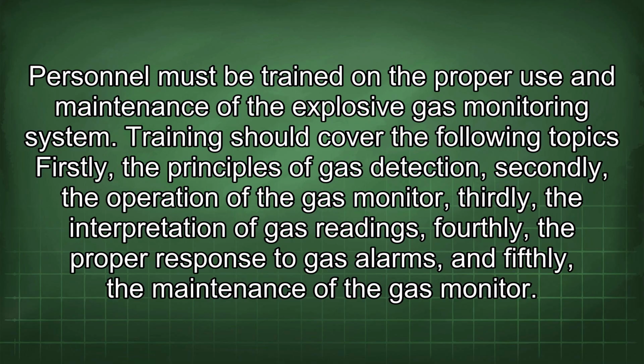Personnel must be trained on the proper use and maintenance of the explosive gas monitoring system. Training should cover the following topics: firstly, the principles of gas detection; secondly, the operation of the gas monitor; thirdly, the interpretation of gas readings; fourthly, the proper response to gas alarms; and fifthly, the maintenance of the gas monitor.